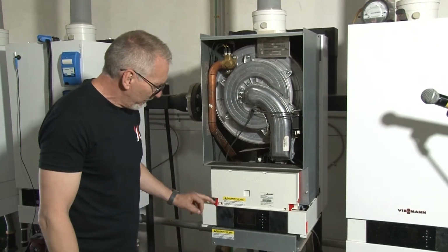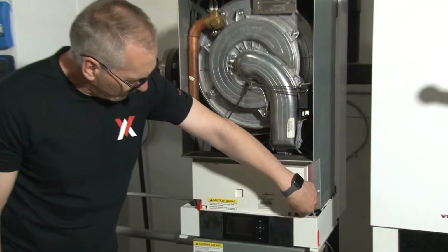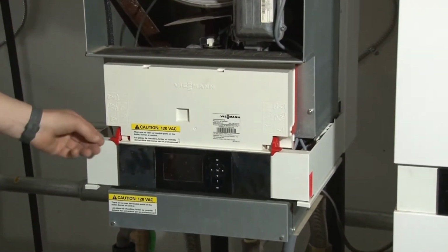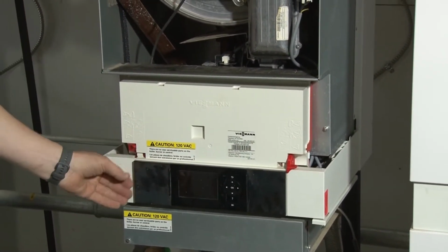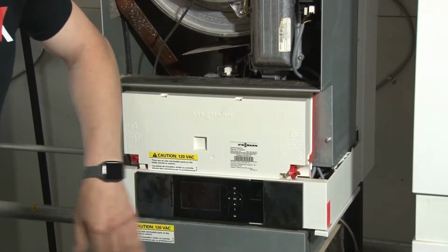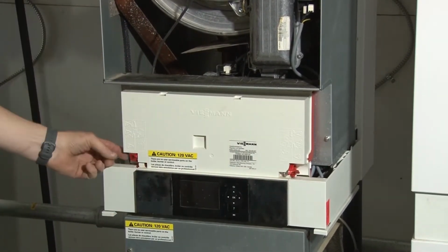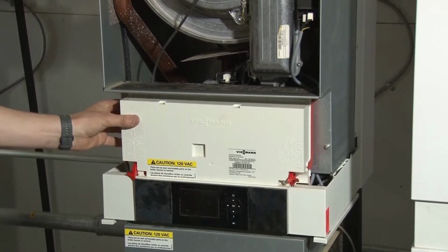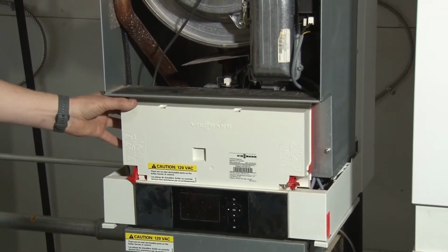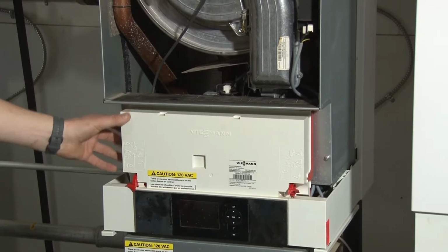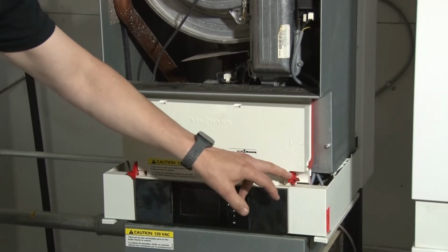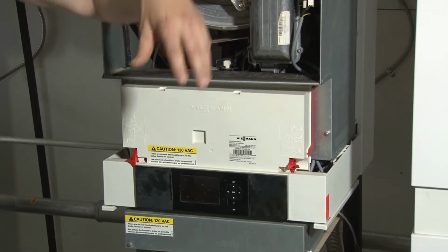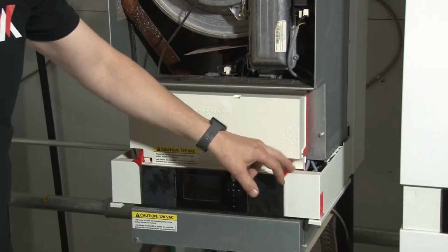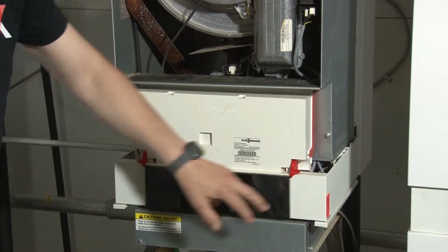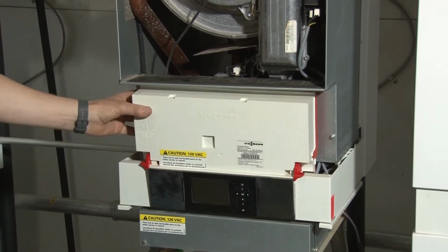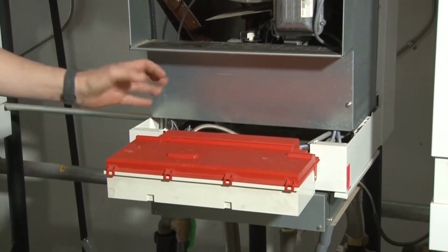Once we have those two things done, we've got these little red clips on the side of the control. We tilt those down. Important, if these little barn doors here on the side are slid and not quite closed, and these clips don't make it all the way down, you're going to struggle to get that door down. And usually I've seen by personal experience, if I don't get those down nice and tight, these little things will fly like 15 feet in the air, and you're chasing those down to try to put them back on here. So do it right, make sure the little barn doors are closed, pull those clips down, and now we can get that door, or our combustion controller, down.